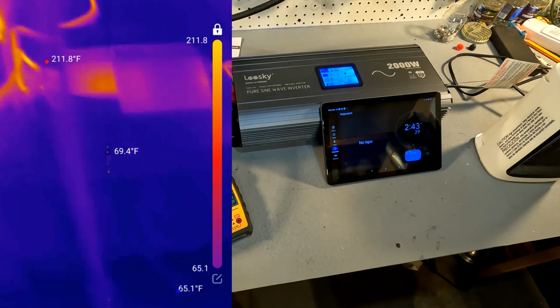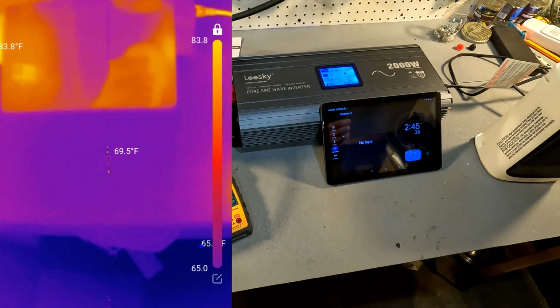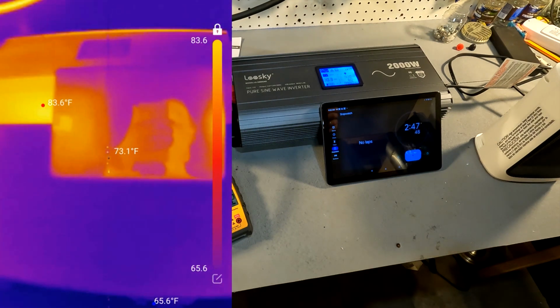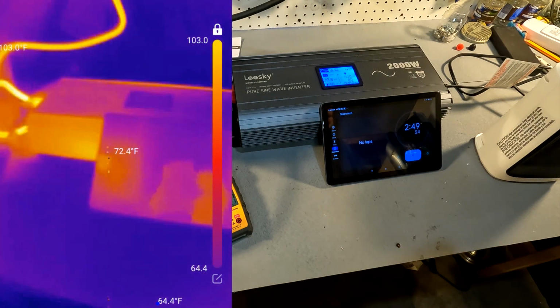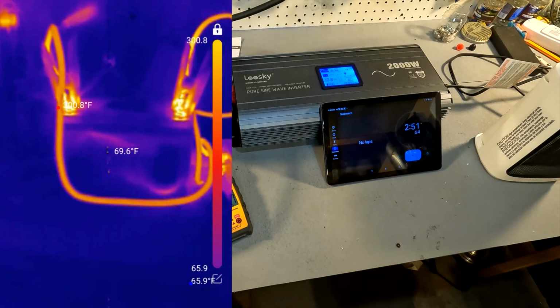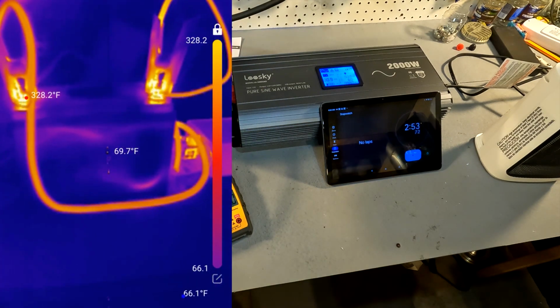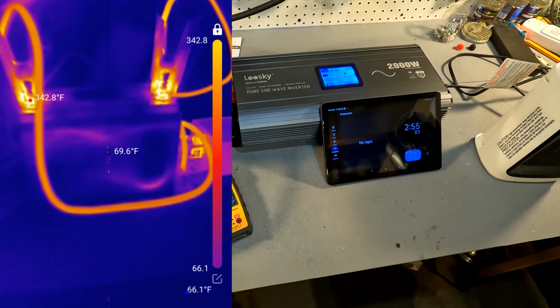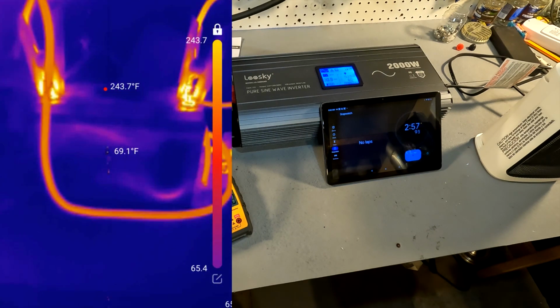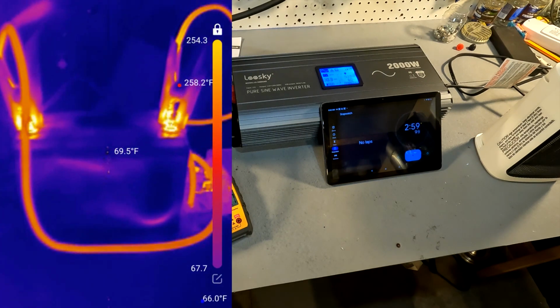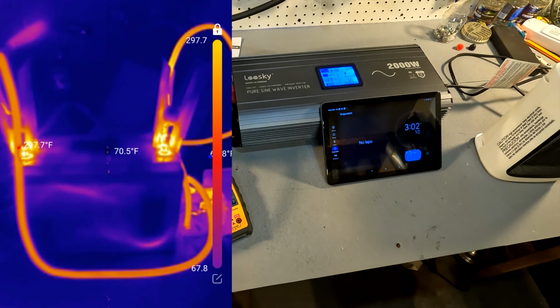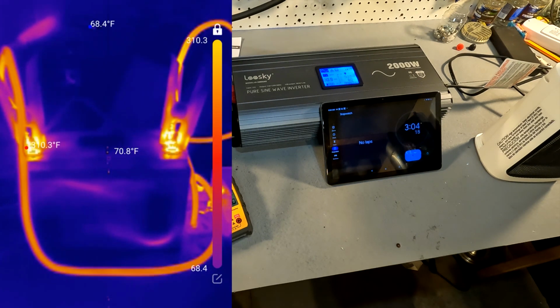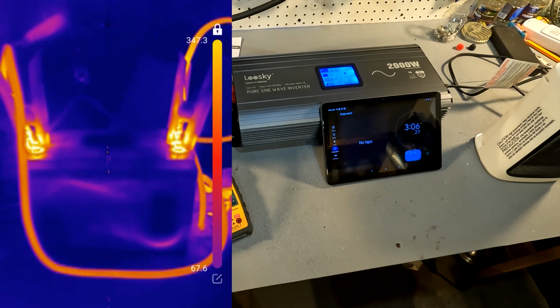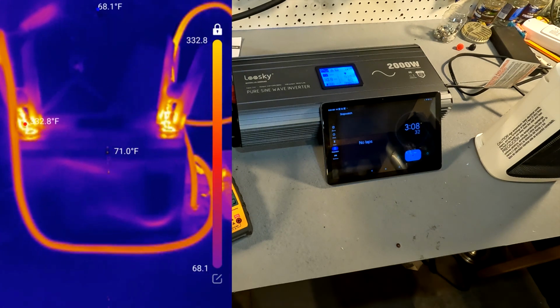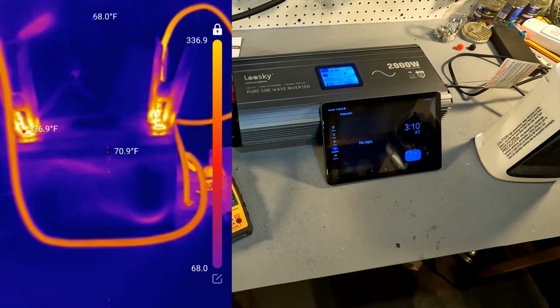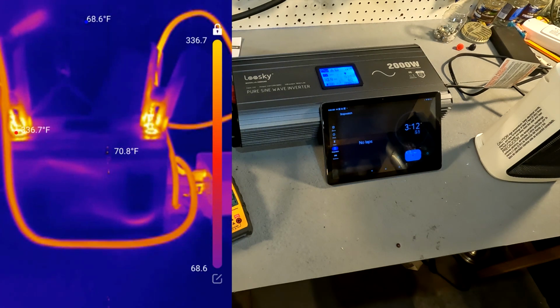Oh, we got a beep. That came from the inverter though. That's showing that the battery voltage is actually down to 10.3. And it's only been 3 minutes now. Yeah, these terminals are hot. Look at that, 300, oh my God, 350 degrees. And this thing isn't shutting off.